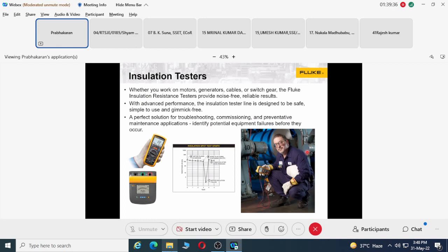That's why you have to do the insulation testing appropriately or as recommended by the standards to ensure that your facility is running appropriately. For that, we have insulation testers for up to 1000 volt, up to 5 kV, and up to 10 kV kind of models. We don't have the very high end ones, but especially for the field usage and for your application, I believe that your insulation voltage levels will be up to 1 kV.